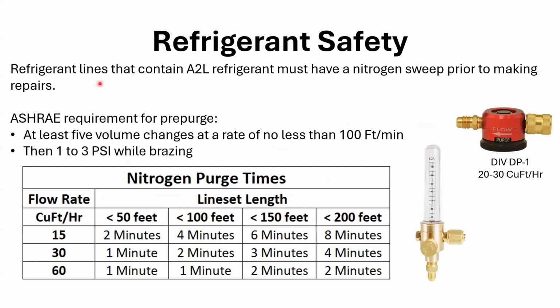Refrigerant safety. Refrigerant lines that contain A2L refrigerant must have a nitrogen sweep prior to making repairs. Yeah, that would make sense, right? If you're doing some brazing or a service repair on a system with 454B and you recover the refrigerant out of it, we always know there's some residual in the system. So doing a nitrogen sweep prior to doing any brazing on it is recommended.